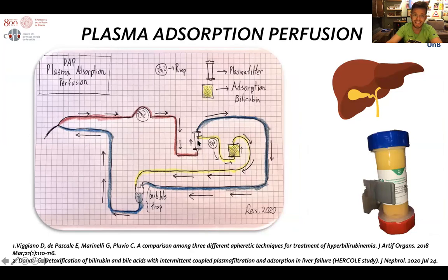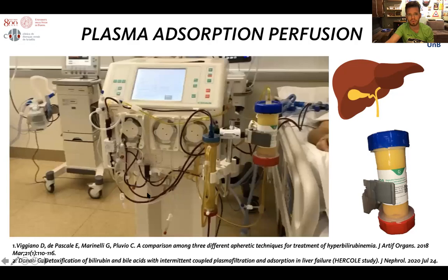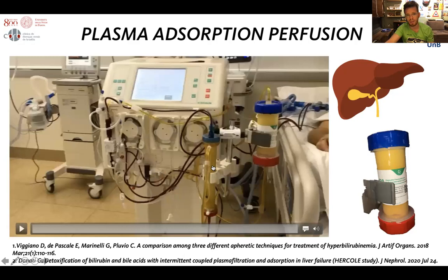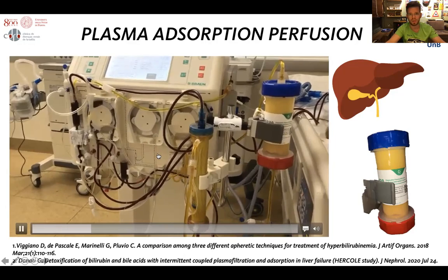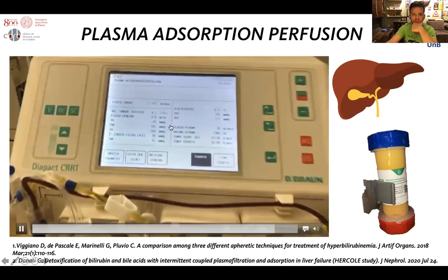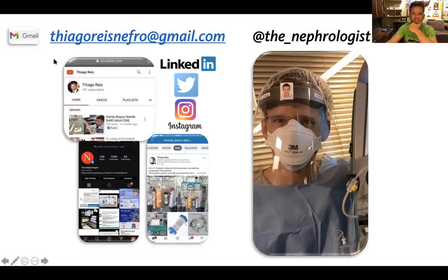Finally, we have plasma adsorption perfusion, a treatment performed in Vicenza. This represents the vascular access: blood goes through the blood pump down into a plasma filter, which drives 30% of the plasma through a separate pump and then through a cartridge with properties to absorb bilirubin and bile acids. They then merge back at the bubble trap. The blood flow is around 150 mls per minute, with 30% of plasma going through the cartridge loop and returning to be reunited with the blood at the bubble trap.